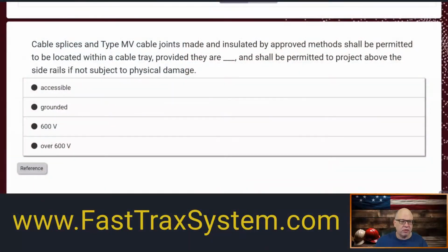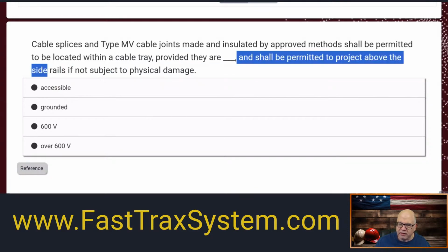All right, so let's answer this question. Cable splices and type MV cable, medium voltage cable joints, made and insulated by approved methods, shall be permitted to be located within a cable tray, provided they are accessible, and shall be permitted to project above the side rails if not subject to physical damage.